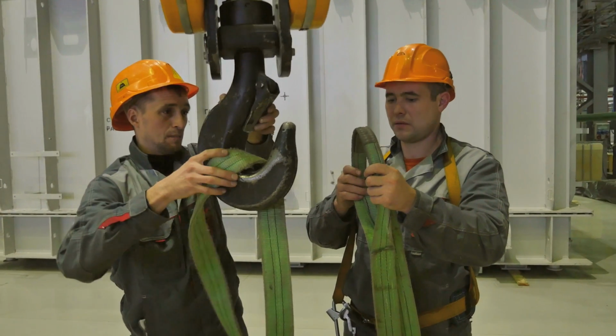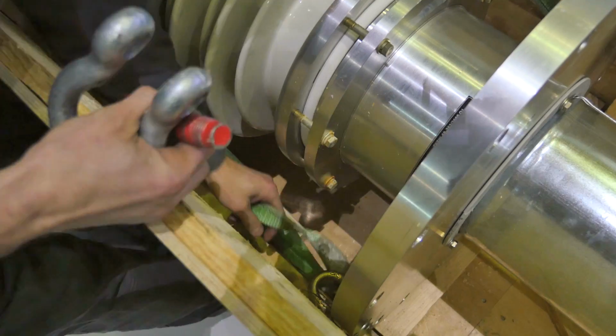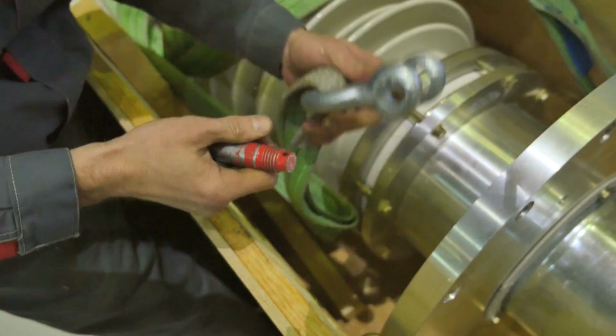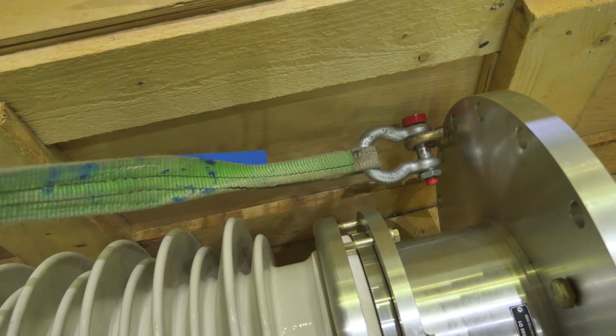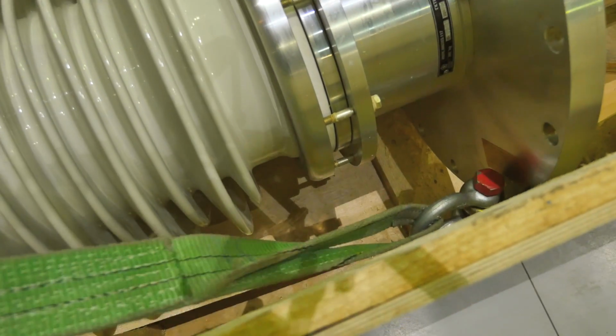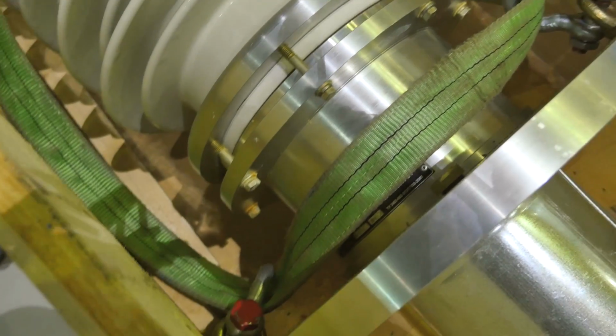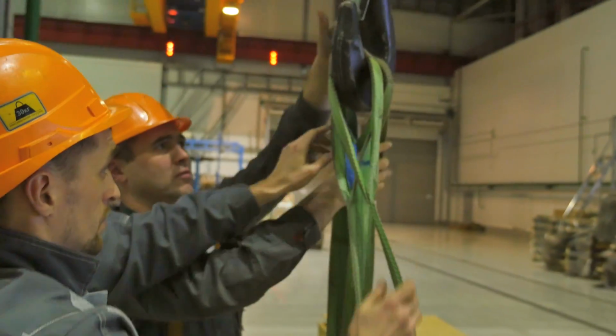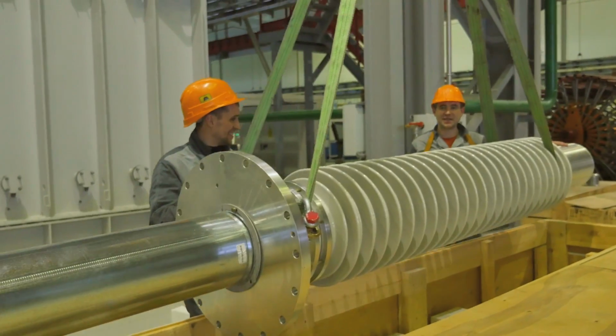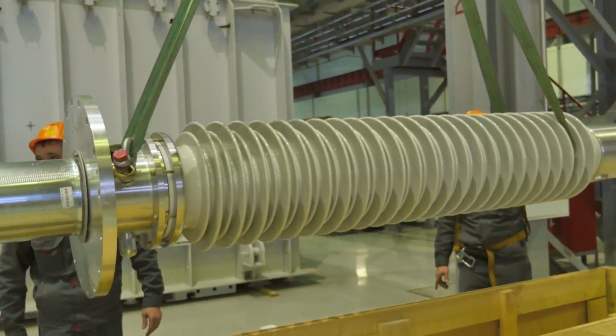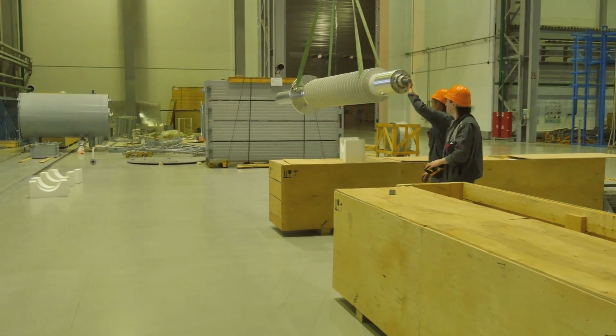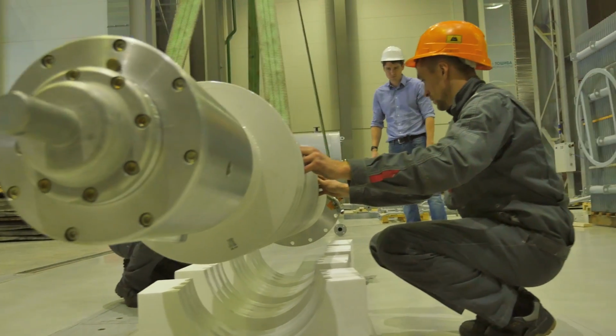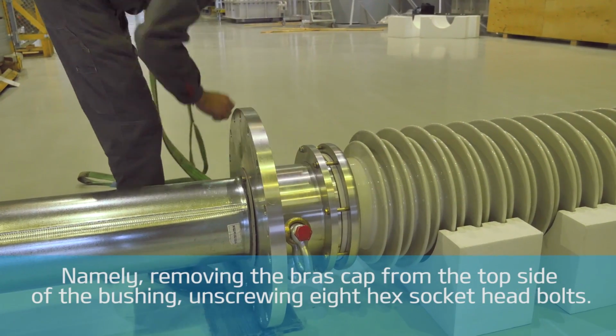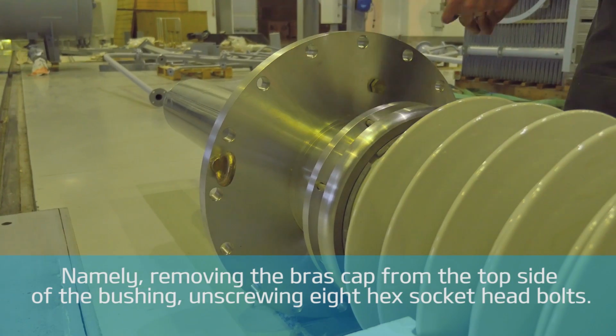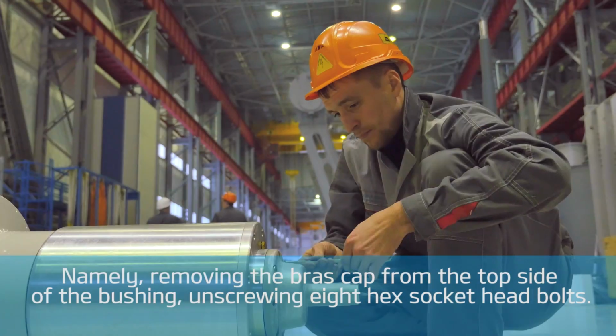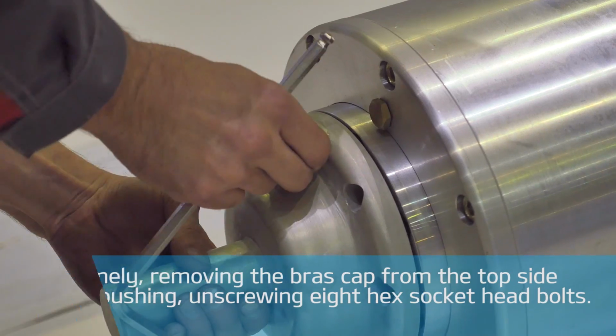There are no critical differences in a draw lead type bushing slinging, removal from packaging, setting on a temporary rack and measurement of internal insulation condition from the same operations on a bottom terminal bushing that we have just detailed. Therefore, we will simply illustrate them with the following frames. Let us study an operation which is not present in the bottom terminal bushing installation works, namely removing the brass cap from the top side of the bushing, which requires unscrewing 8 hex socket head bolts.